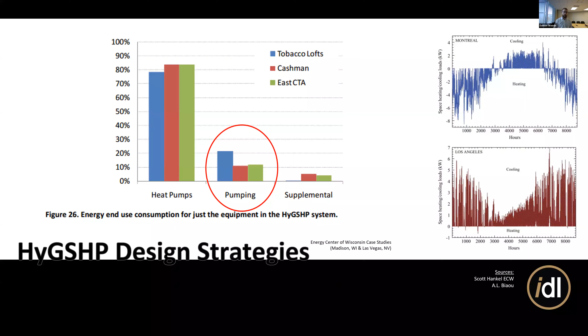The supplemental system actually used very little energy, even though it could have been used for a lot more, to meet those worst case scenarios. It looks like Tobacco Lofts, that apartment complex, never had to be tripped on for that particular year. And the indoor system, this is our compressor or our evaporator coil or compressors, depending on which mode they're in, fans, all that. But then we've also got to move all of that water and glycol through our heat exchanger, through all that pipe that we buried in the ground. And that can be a really significant portion of the energy.